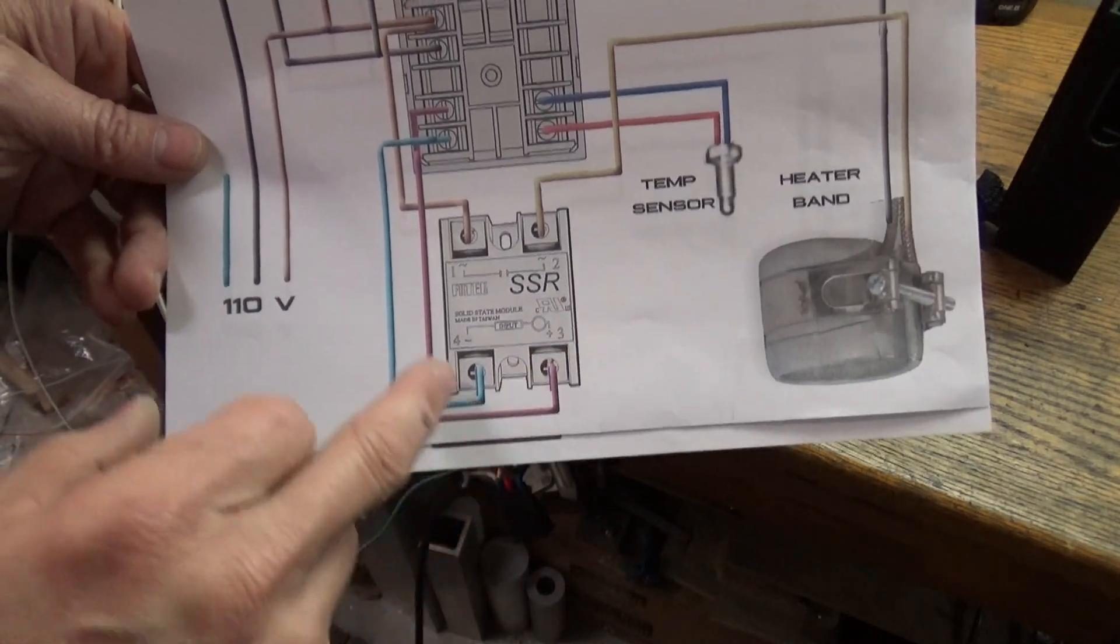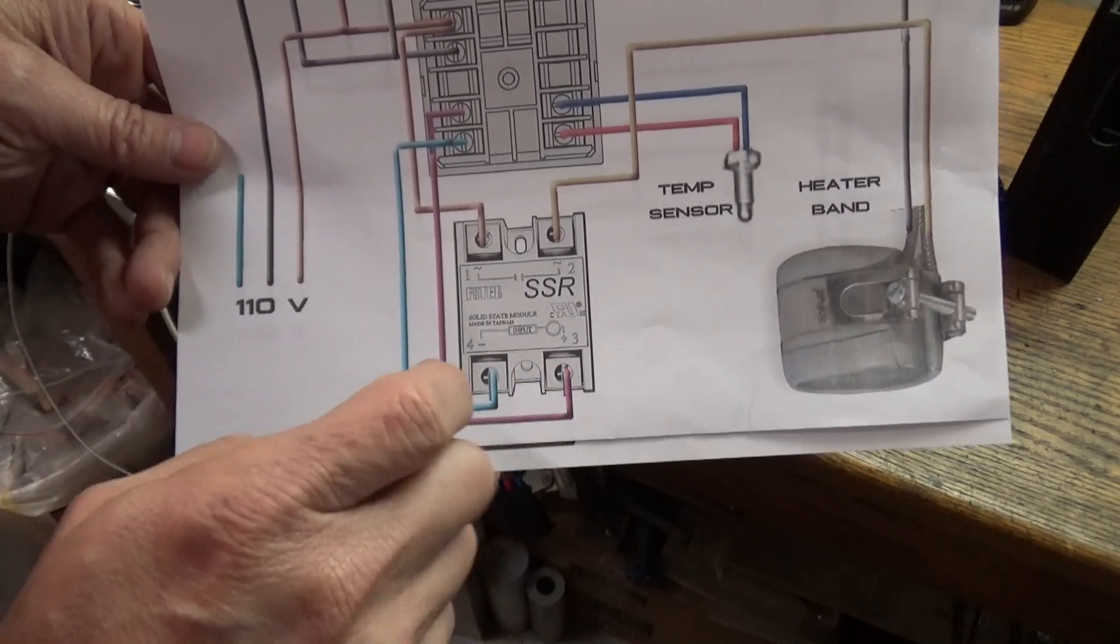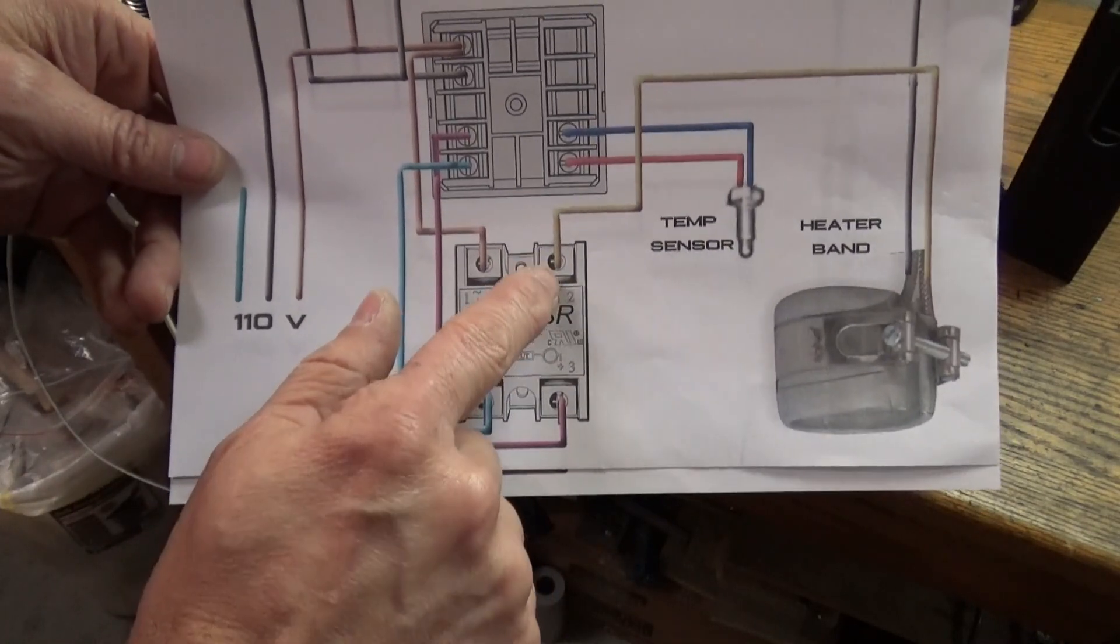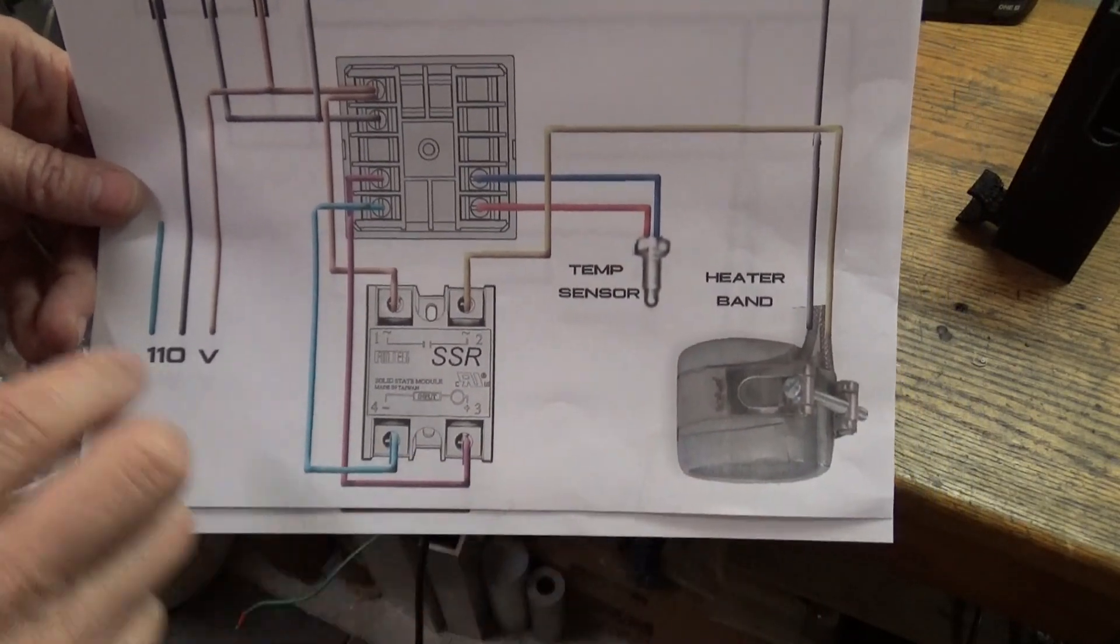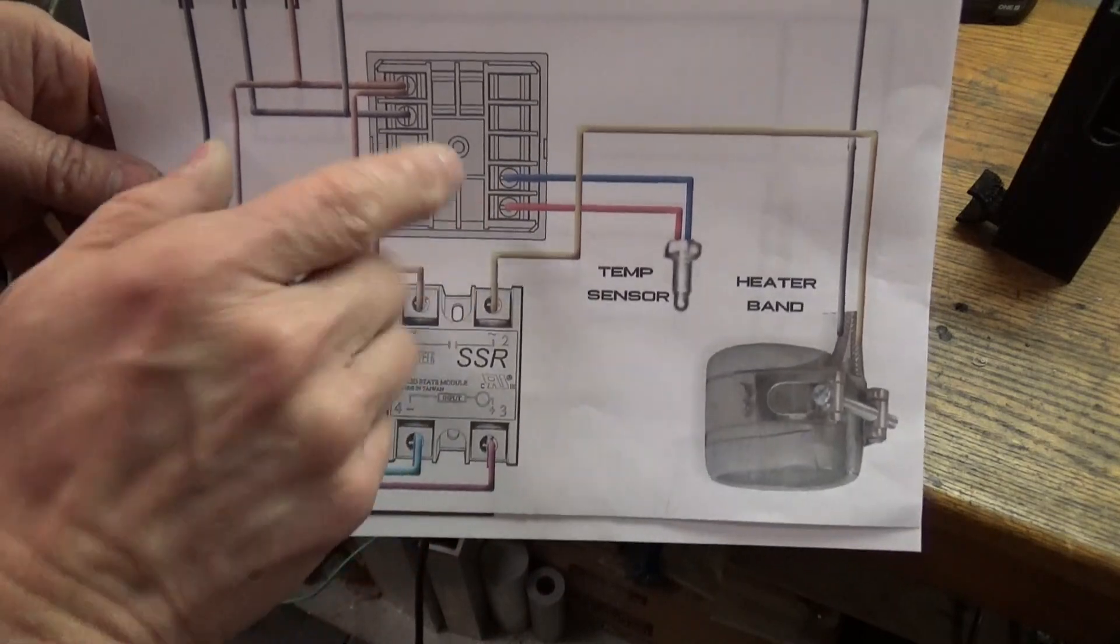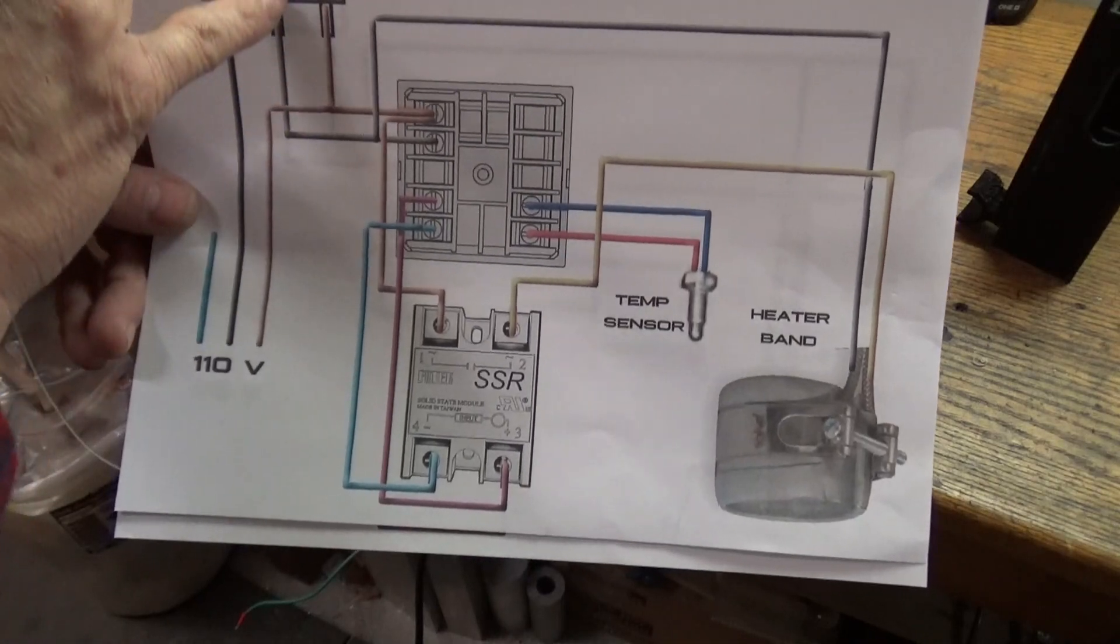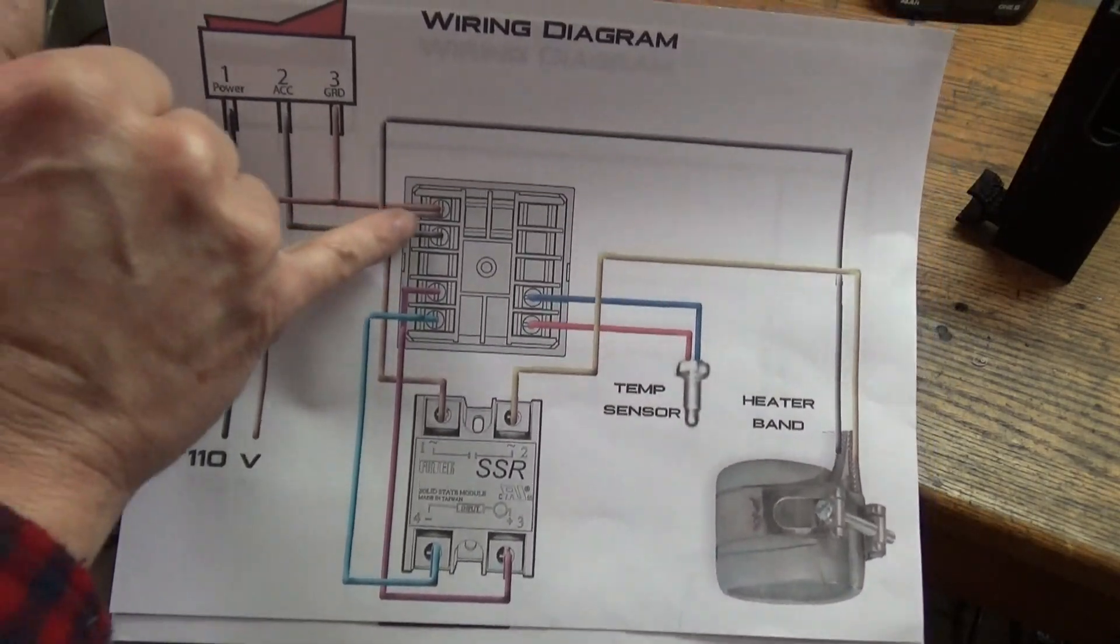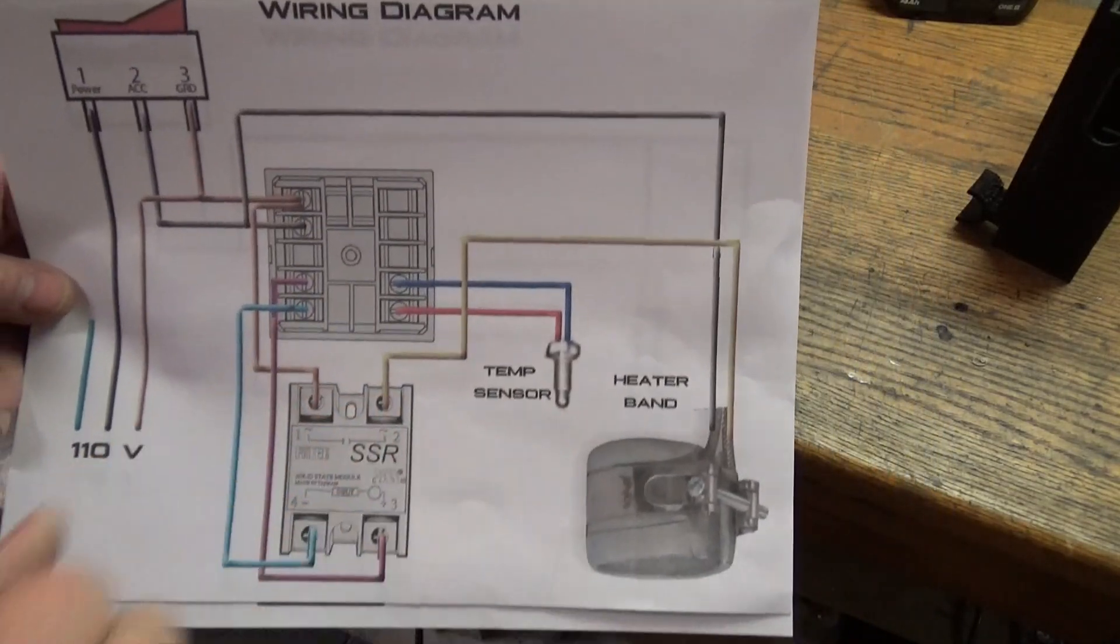To switch the relay here we have this purple and blue wire, and then coming out of the contacts of the relay we're going over to our band heater. Our temperature switch is just wired to these two connections here. On the switch side, our 110 volts goes to this terminal and then also goes over to the band heater.